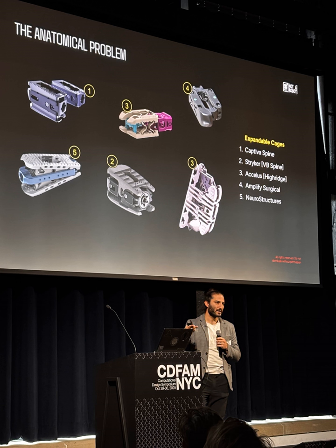And certain other things become important in designing these sort of things, like where is the bone the stiffest? We want to be able to land the implant on spots that we know are going to be supported over the life of the individual. So if you put it on too soft of a spot, you get what's called subsidence. The implant pushes into the bone. That's bad, generally requires a revision surgery and huge problems for the patient down the line.